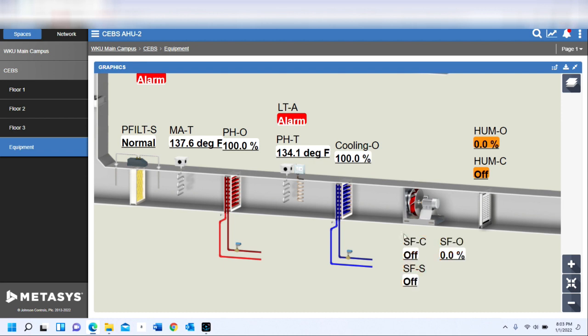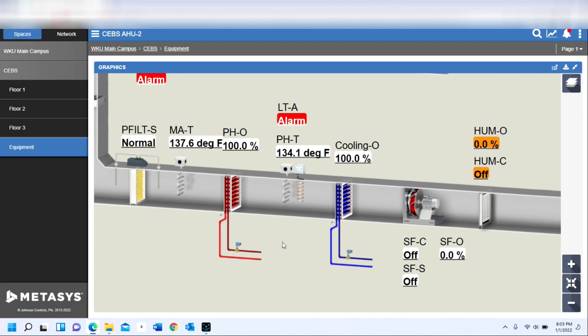Just ignore this—I know this air handler is off, it's actually shut down for the moment. But if we had an air handler discharging high with the valve calling for 100, the first step we're going to take after that is probably going to be to check the chilled water system. So instead of having to go back all the way through my navigation, I can simply link the coil here to the chilled water system.